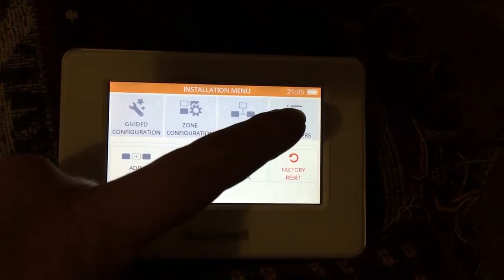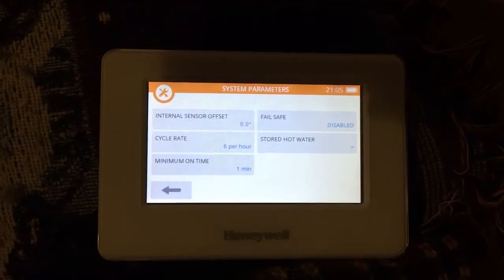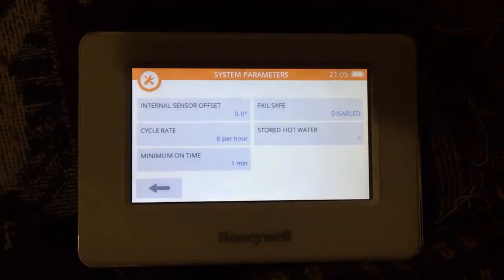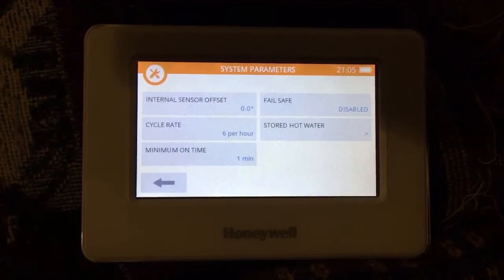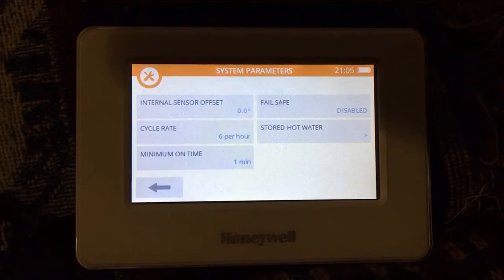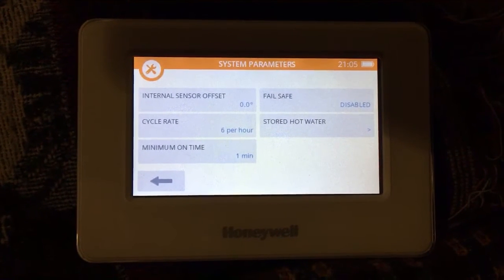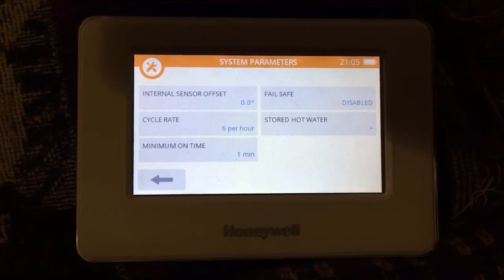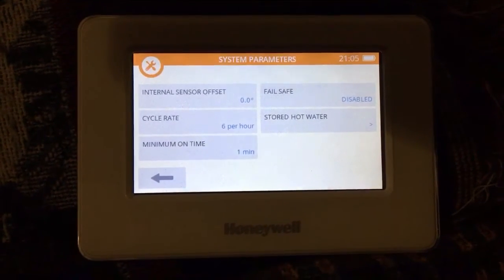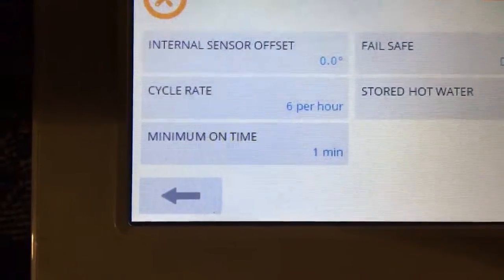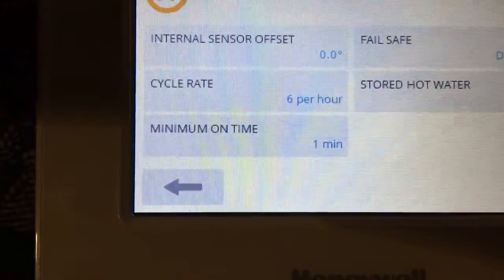But this video is looking at the system parameters. So if we open system parameters, we've got several parameters that we can change. One is sensor offset, and we've got cycle rate, run time, fail safe and stored hot water. And this one we're going to look at the cycle rate and minimum run time.